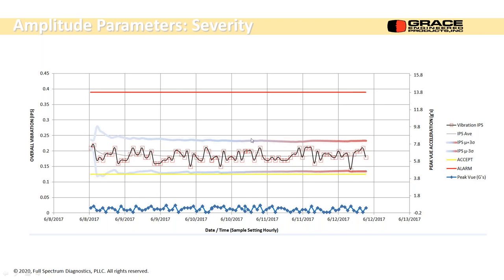And by the way, I do want to have alarms in both directions. These alarms are set by a mean plus 3 sigma distribution. So the mean value, the average value, plus or minus 3 standard deviations. And that's what gives me these curves on either side. The top one, I want to know if vibration goes up, I want to be able to detect that. But also, I want to detect if vibration goes down. If I go from 0.175 inches per second, and I drop down to 0.1, something changed, something happened. It might not be good.